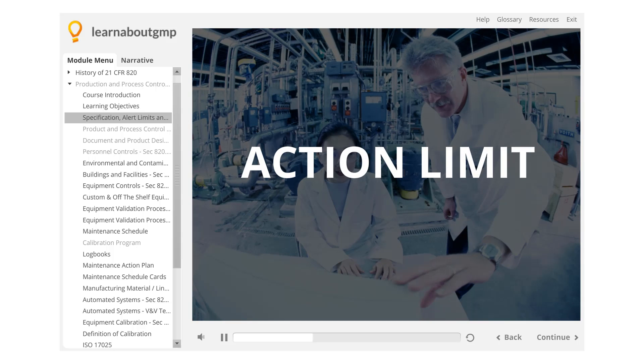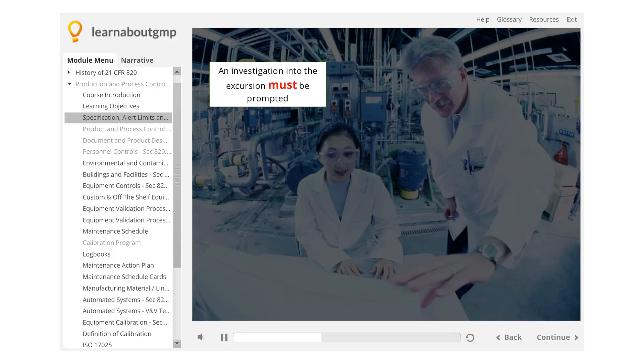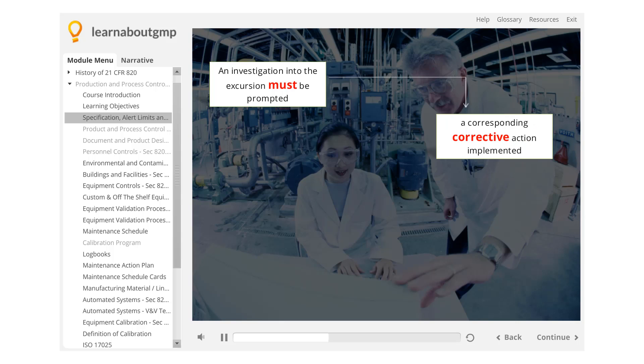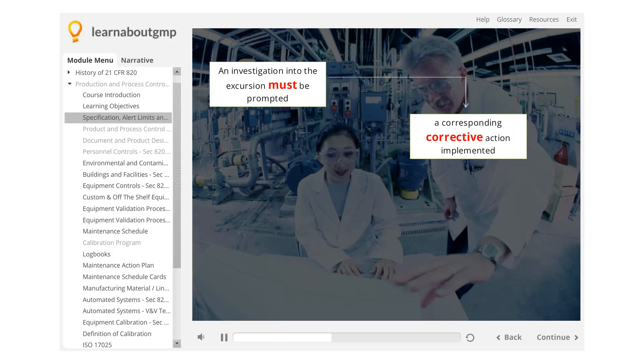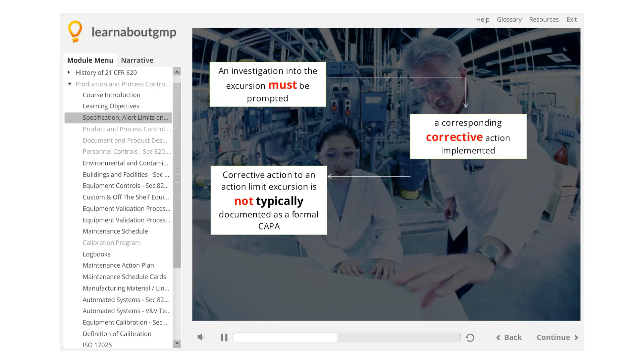The next level is the Action Limit. Once a process or product exceeds the action limit, an investigation into the excursion must be prompted and a corresponding corrective action implemented if possible. It should be noted that a corrective action to an action limit excursion is not typically documented as a formal CAPA — corrective and preventative action — but is managed within an SPC process.